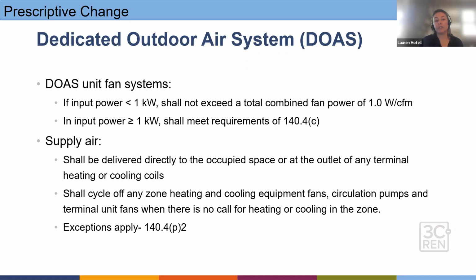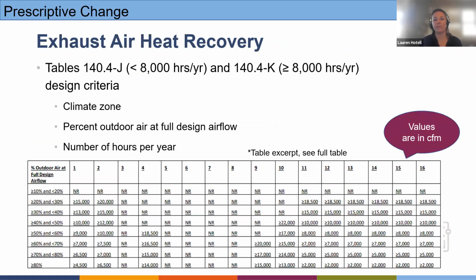The supply air should cycle off any zoned heating and cooling equipment fans, circulation pumps, and terminal unit fans when there's no call for heating or cooling in the zone. This is for certain climate zones, and certain air handler design scenarios may also require exhaust air heat recovery, which I'll jump into.